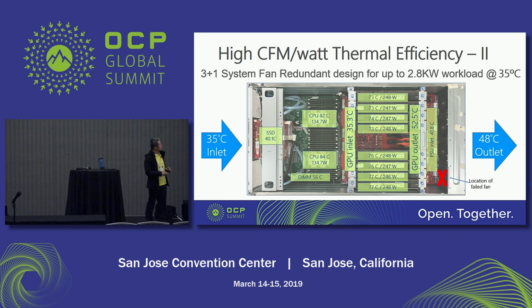You can see that the temperature difference is not much, or even equal. And after the PCIe cards, with the NVIDIA V100 card we tested, the PCIe outlet temperature is 52.5 degrees C.